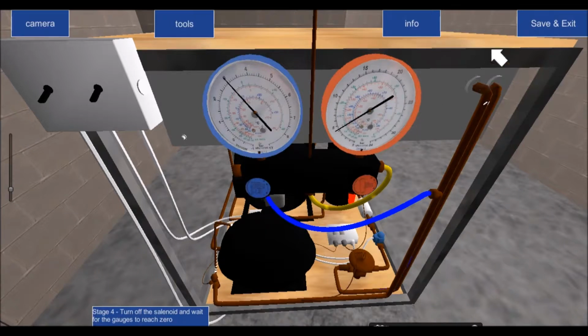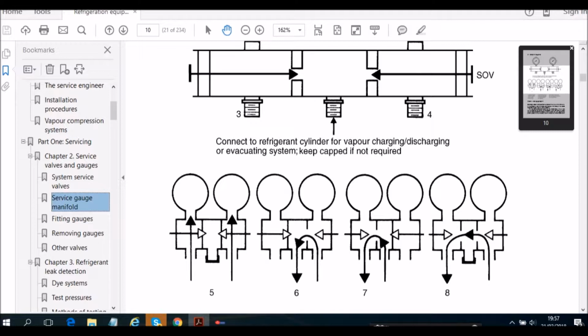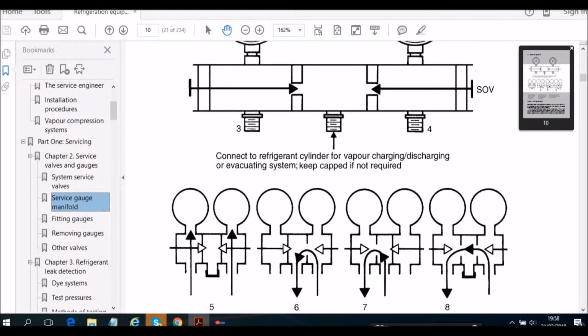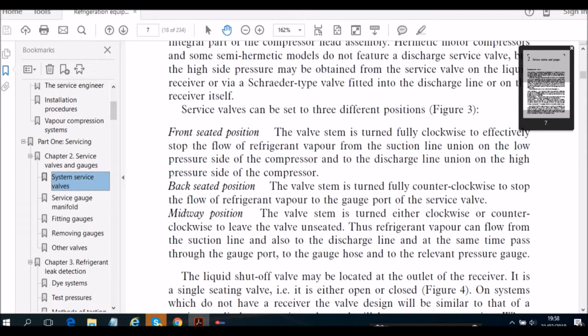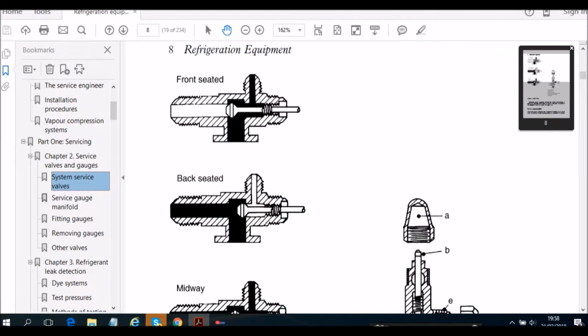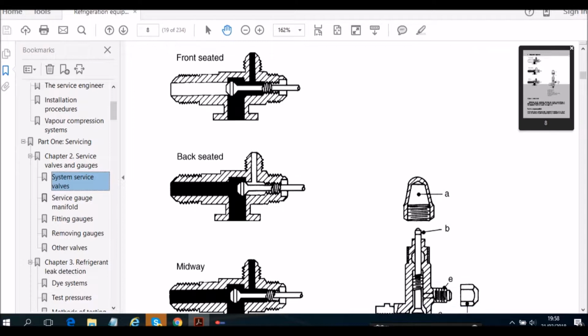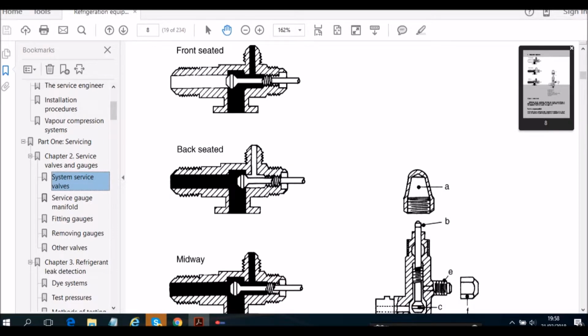And effectively what that means is that because I've opened this shut-off valve and this shut-off valve, high pressure has come from the red hose across into the service area, into my yellow line, and across into my blue line. Now, because I had my valve in the back-seated position, when we go back to my valve here, in the back-seat position, no new refrigerant is coming from the liquid receiver.